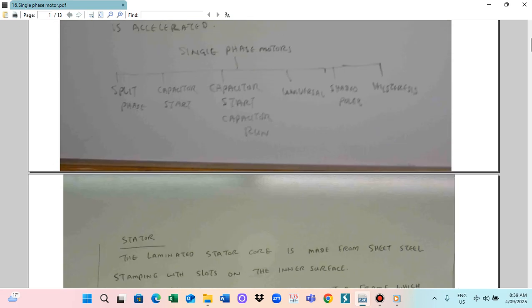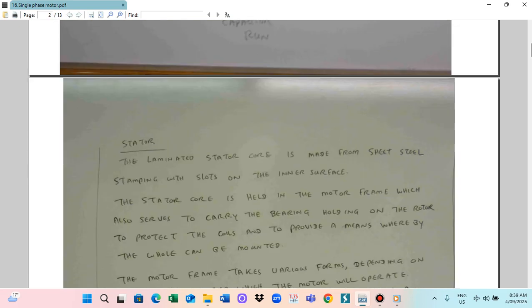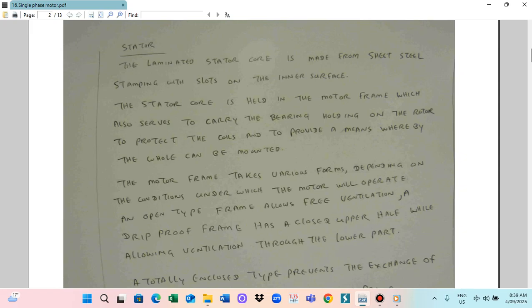The laminated stator core is made from sheet steel stampings with slots on the inner surface. The slots are already formed, and the stampings are set together. The stator core is carried in the motor frame, which also carries the bearings holding the rotor, protects the coils, and provides the means whereby the whole can be mounted. So the motor stator functions to hold the coils as well as to mount the bearings.